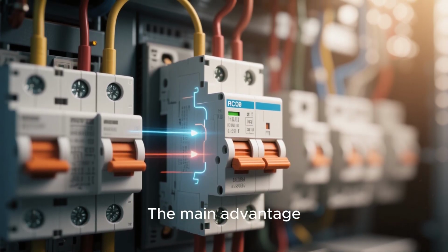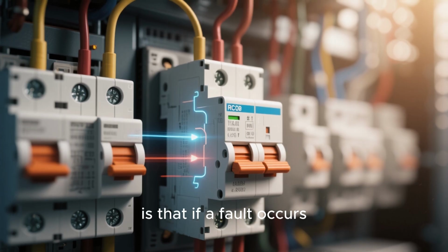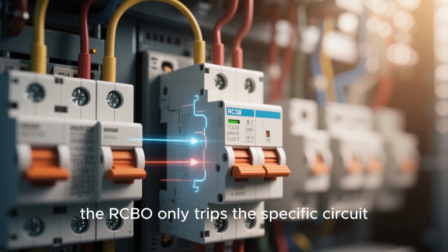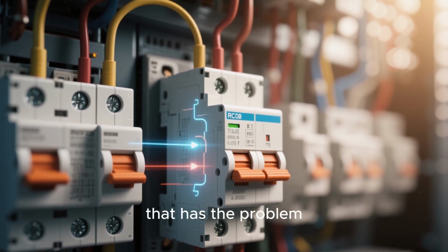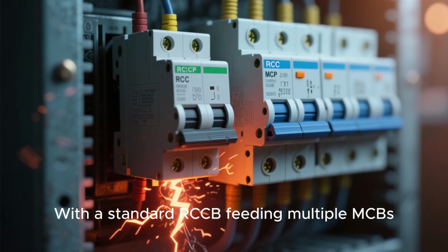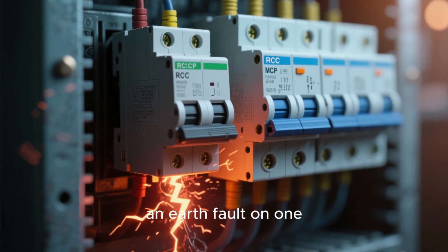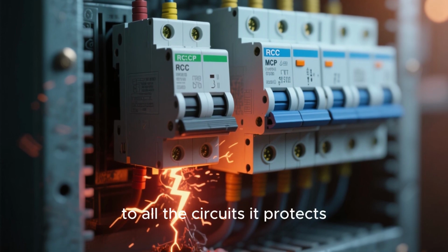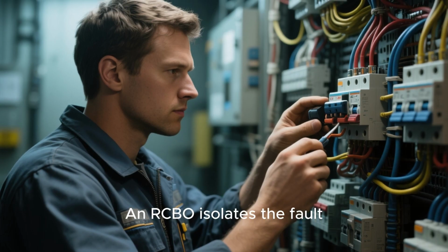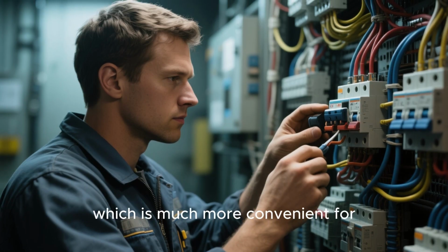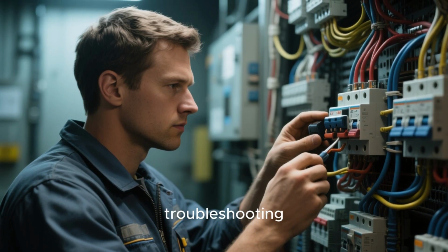The main advantage is that if a fault occurs, the RCBO only trips the specific circuit that has the problem. With a standard RCCB feeding multiple MCBs, an earth fault on one circuit would trip the RCCB, cutting power to all the circuits it protects. An RCBO isolates the fault, which is much more convenient for troubleshooting.